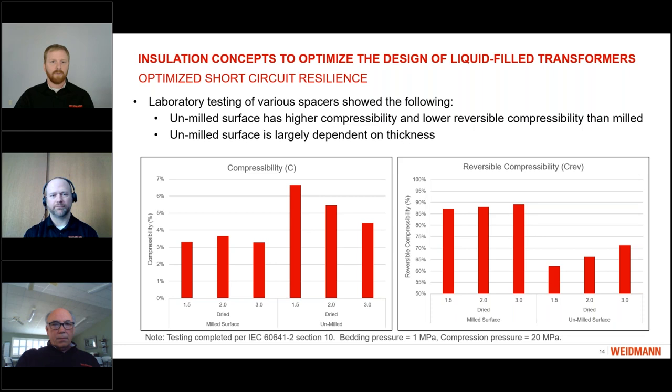So when we look at these materials in the lab, we did some laboratory testing of various spacers and looked at a number of different things regarding compressibility. Just for reference, this testing was all completed per the IEC standard. So we're using a bedding pressure, an initial pressure of the spacer stack, of 1 MPa, and then compressing that stack up to a pressure of 20 MPa and measuring the difference between those two.